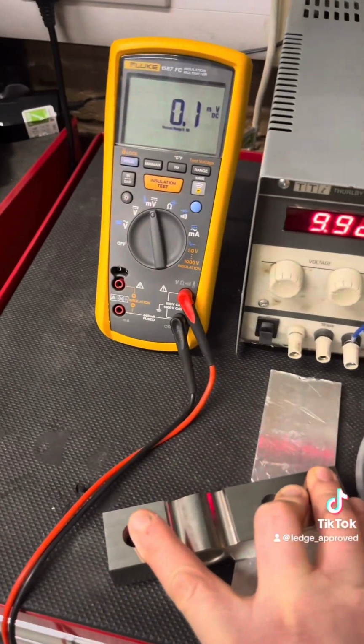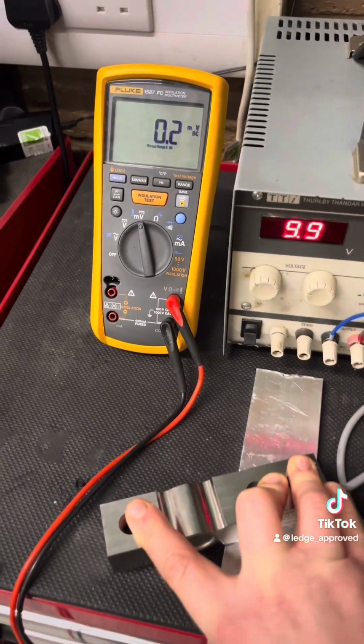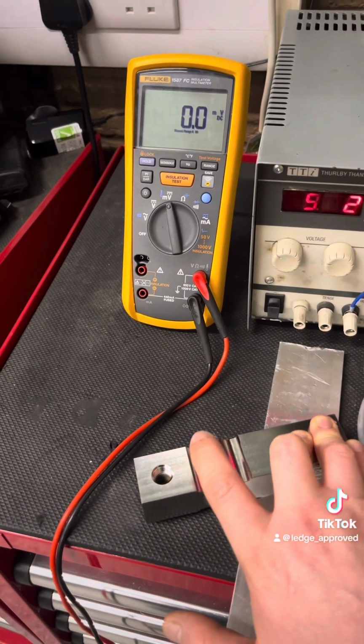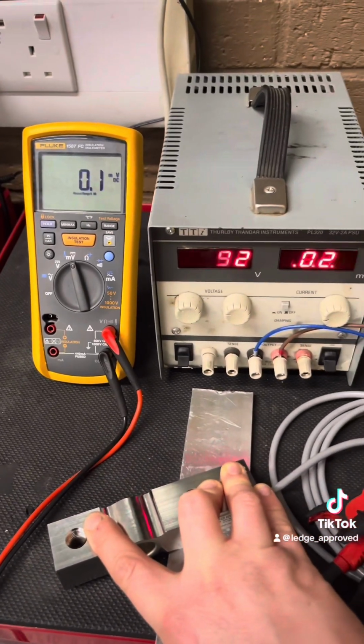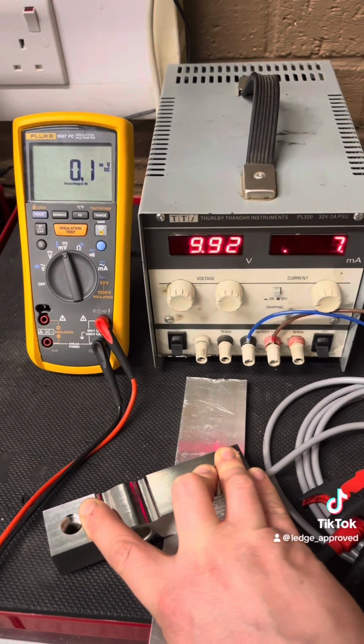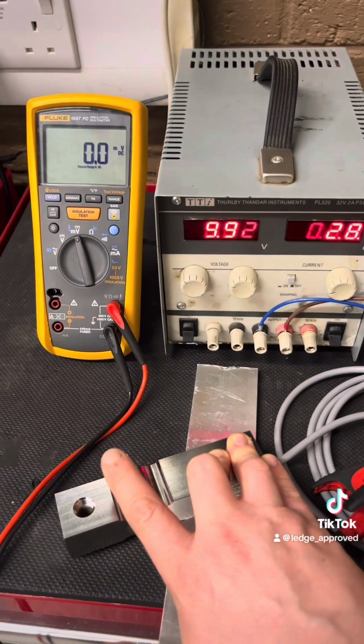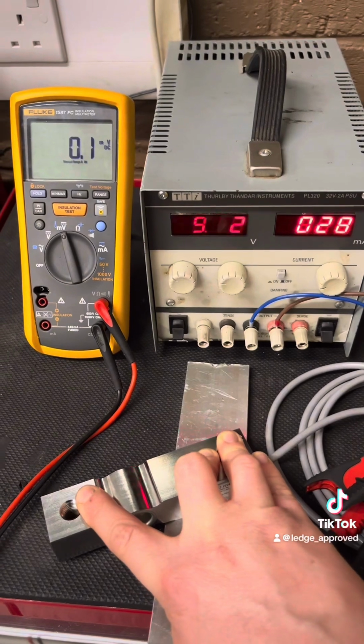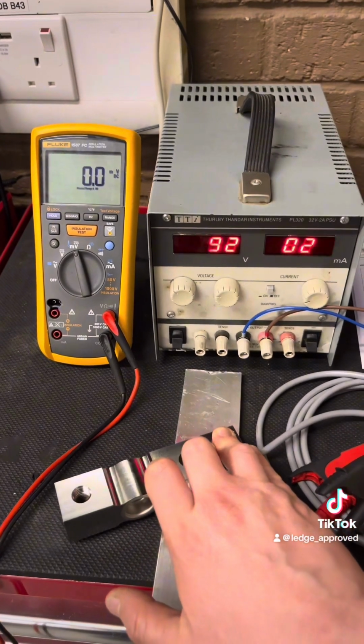So then what I'm going to do is just apply a little bit of pressure. What you would want to do is put a known value weight on there that the calibration sheet has shown. And then you want to get it to what it actually is on the actual sheet itself. But you can see the millivolts going up and down as I apply a little bit of pressure.